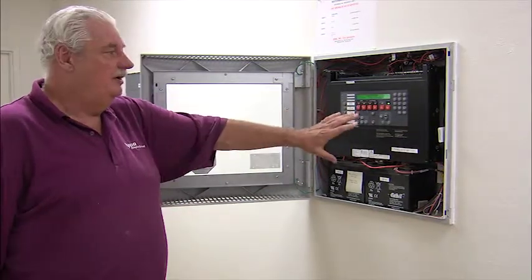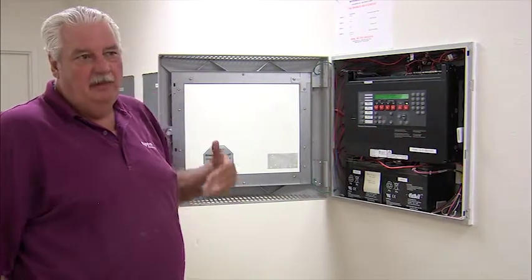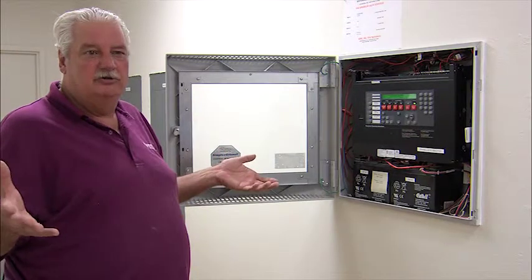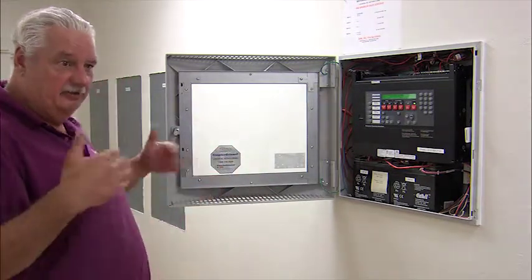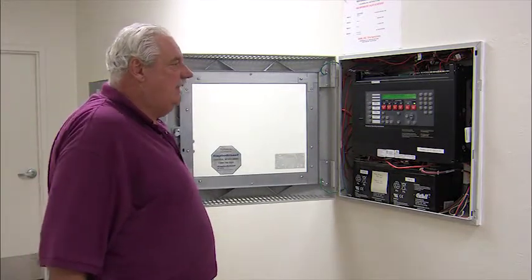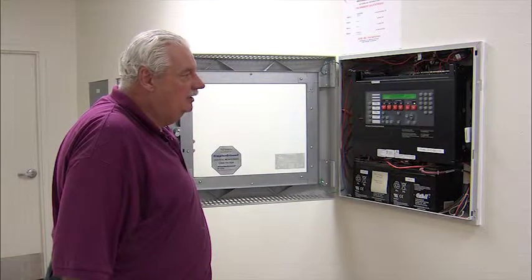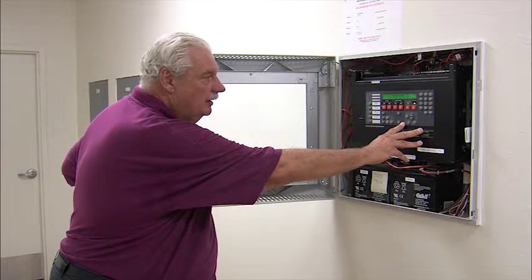And the best thing to do on those is, if you get a duct detector, acknowledge it. And if you know it's because somebody turned the heat on finally, give it a minute or two to clear out, because all that dust will have gone through the detector and it takes a minute to settle. That is that. Other than that, I don't know anything else to let you know on here.